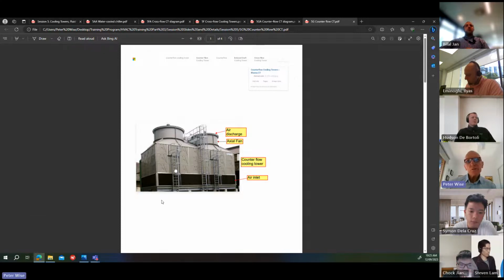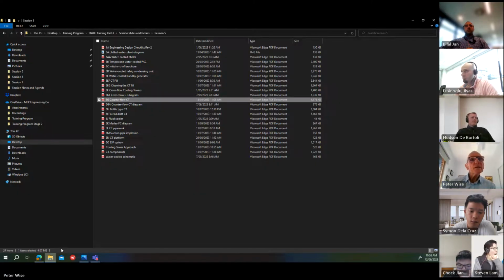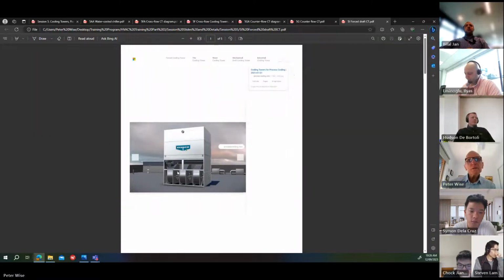Now you can have induced draft, which is typical. These towers here are induced draft, which means the air is drawn through the cooling tower and discharged out the top. But you can also have a forced draft cooling tower. So that's a picture of one. This one's got centrifugal fans at the bottom, which blow air up through the fill. So it's basically the same thing, but the air is being blown through the fill and then out the top.